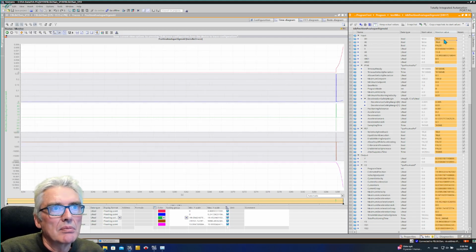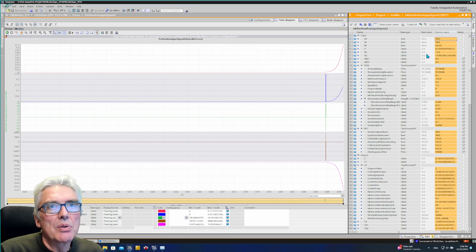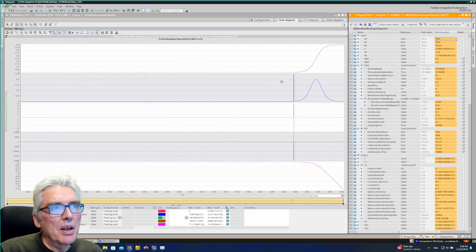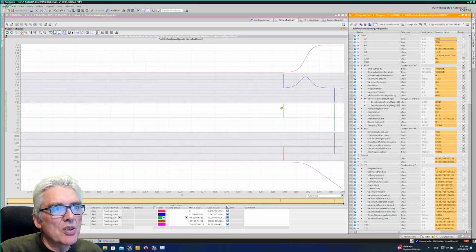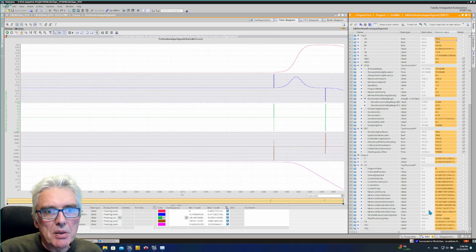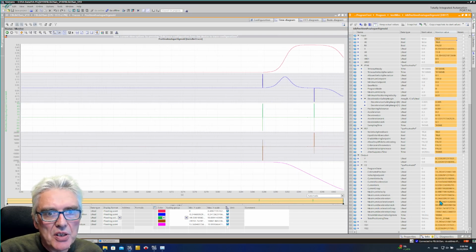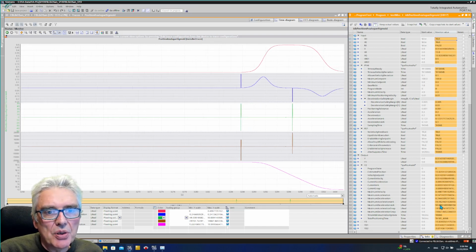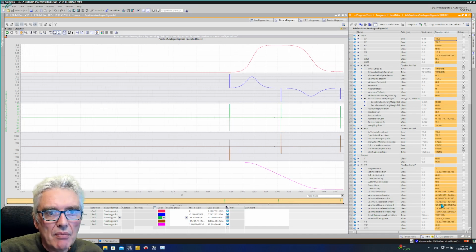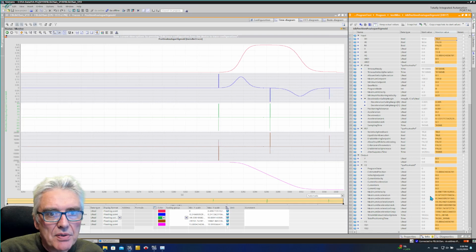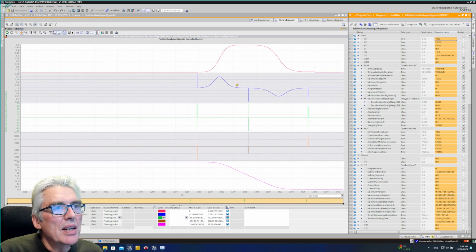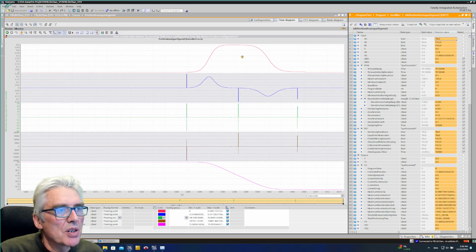The reason it's like that is you could just change the set point here without the program starting. Now you can see you get spikes here. And for the jerks, the spikes are pretty high. If you look at the maximum acceleration jerk, it's 49. Maximum deceleration jerk is 50. And the acceleration was 0.24. It should be 15 here or something like what is specified here.